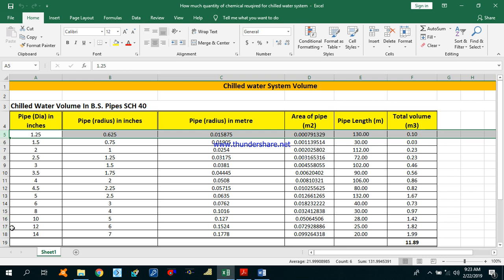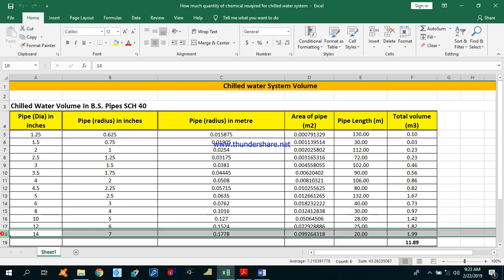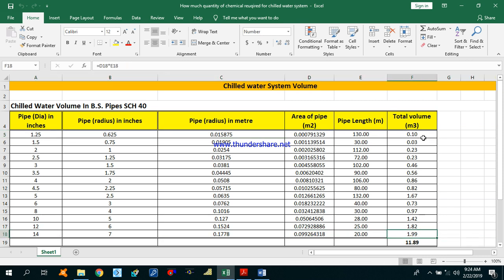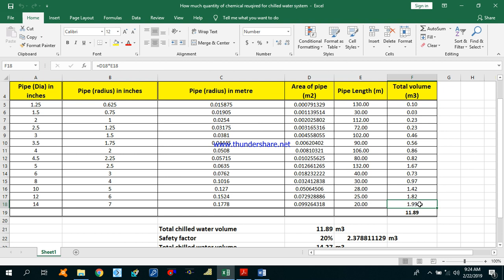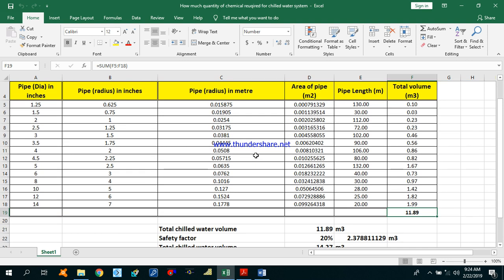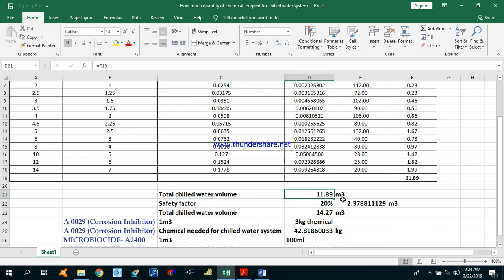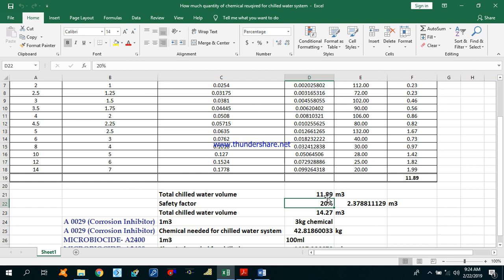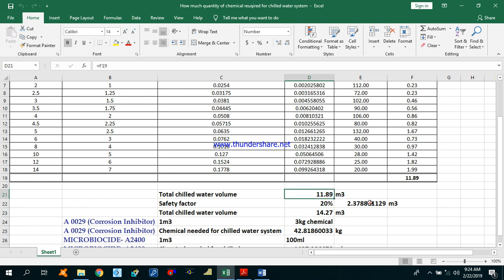In the same way you calculate for all pipes used in the project. For 14 inches with 20 meter length, that is 1.99 cubic meters. Now you sum all of these volumes and you get 11.89 cubic meters total chilled water volume. Now we apply a 20% safety factor — 20% of 11.89 is 2.37 cubic meters — giving a final total of 14.27 cubic meters.